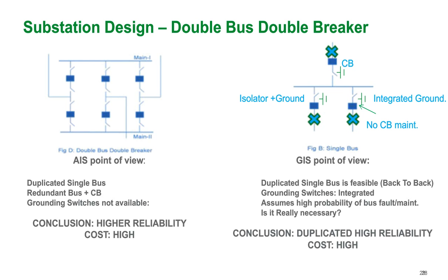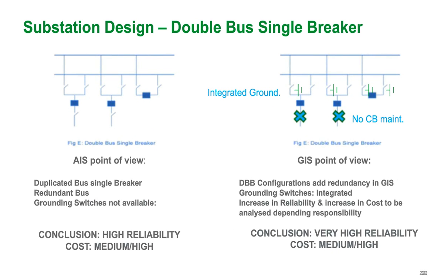Second to last one here, double bus and a single breaker. So this is a selective bus bar arrangement where a single circuit breaker can select from an A or B bus bar source. From an air-insulated switchgear point of view, you get high reliability here. The cost here is lower than that double bus, double breaker arrangement. So this is where one of those cost analyses really has to be done as far as reliability and cost, because the cost here is lower than your double bus, double breaker, but it's still quite high.